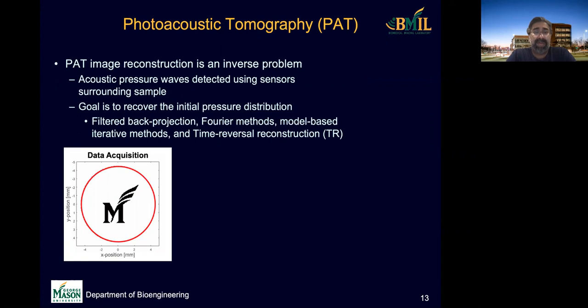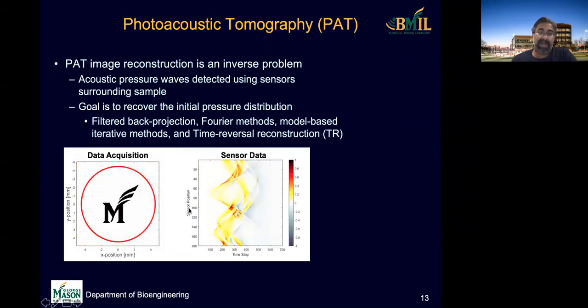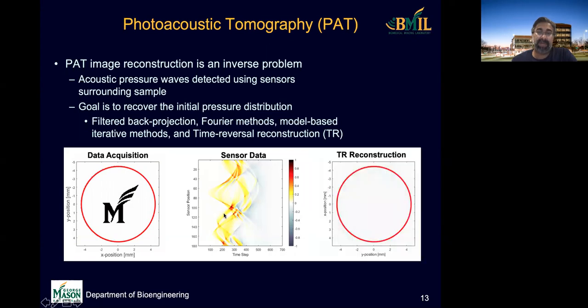But the reconstruction of the image is then an inverse problem. So if we have an object like this that we're imaging, and we're using a large number of sensors that surround the object here, then the photoacoustic waves will propagate from the object. We detect them with the sensors, and here's our sensor data. And we can use this sensor data to reconstruct an image with methods, for example, time reversal reconstruction, and we get an image like that.